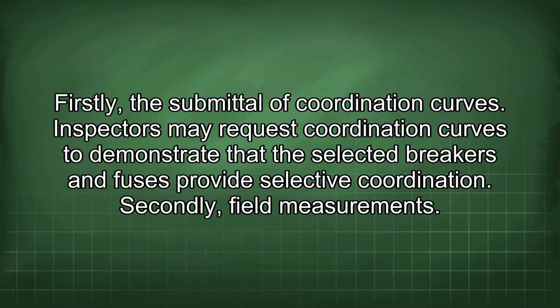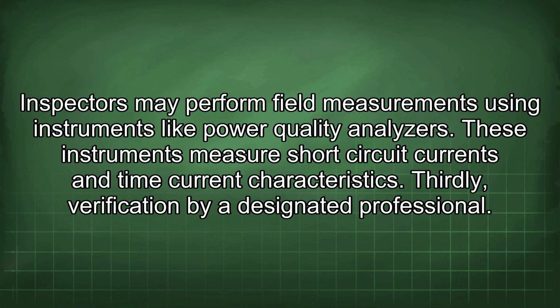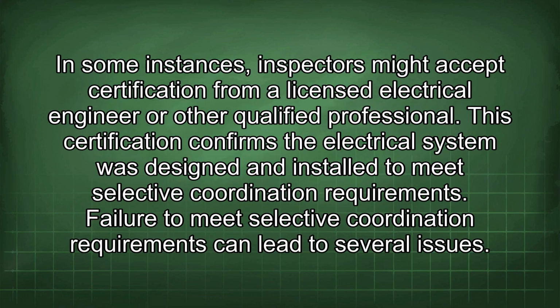Secondly, field measurements. Inspectors may perform field measurements using instruments like power quality analyzers. These instruments measure short-circuit currents and time current characteristics. Thirdly, verification by a designated professional. In some instances, inspectors might accept certification from a licensed electrical engineer or other qualified professional. This certification confirms the electrical system was designed and installed to meet selective coordination requirements.